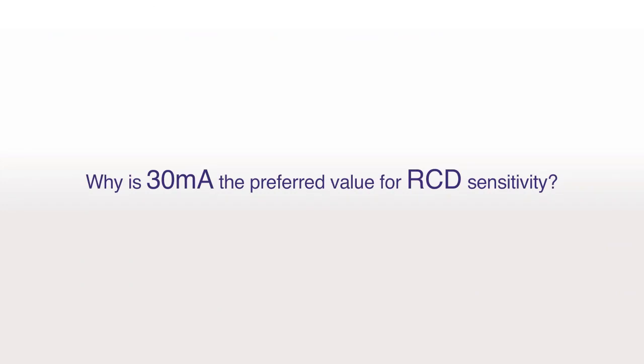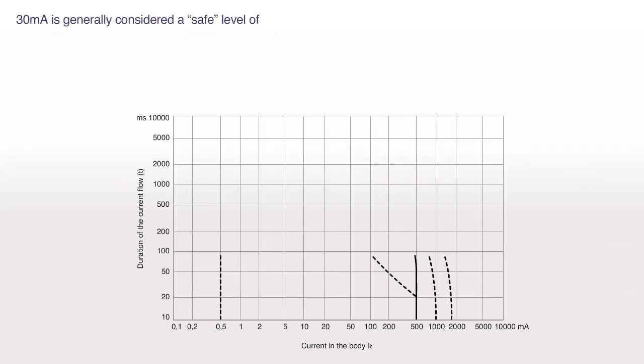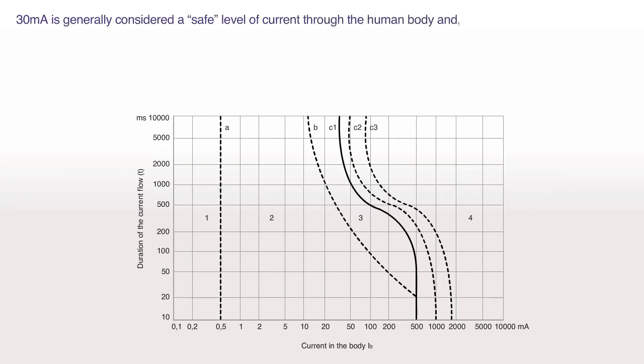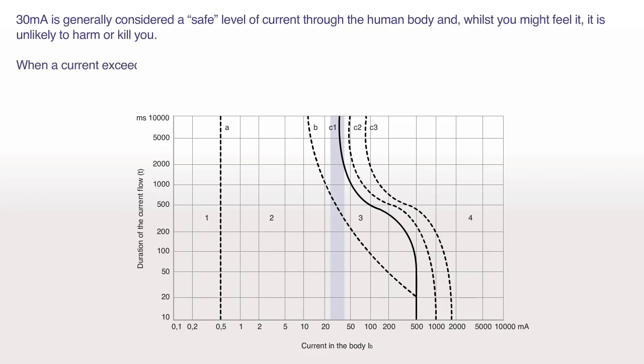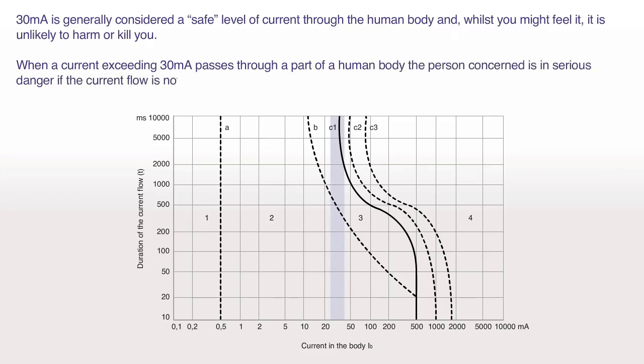Why is 30 mA the preferred value for RCD sensitivity? 30 mA is generally considered a safe level of current through the human body, and whilst you might feel it, it is unlikely to harm or kill you. When a current exceeding 30 mA passes through a part of the human body, the person concerned is in serious danger if the current flow is not interrupted in a very short time.